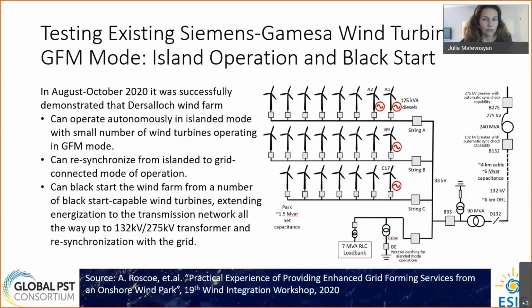Initially, the tests were done to just operate auxiliaries of the wind farm, not having any load supplied. And then they also tested load steps of 7 megawatt, where they connected a 7 megawatt load bank. And again, in all the tests, successful operation as expected was demonstrated. And then they were also able to successfully resynchronize the island from islanded grid back to grid mode operation.